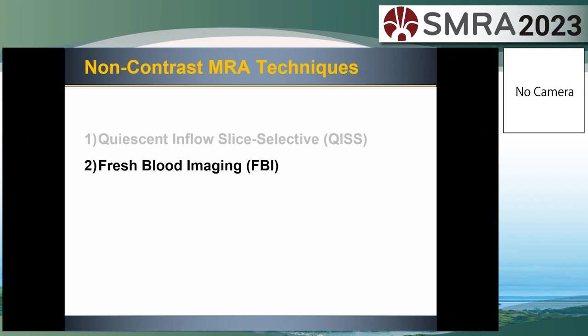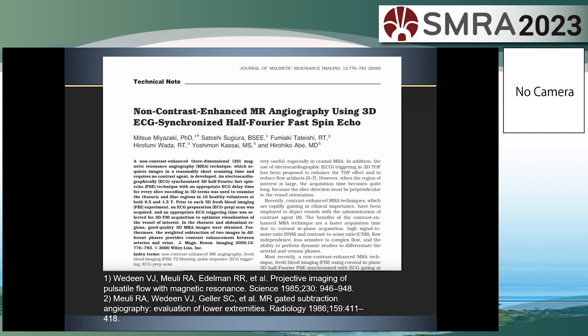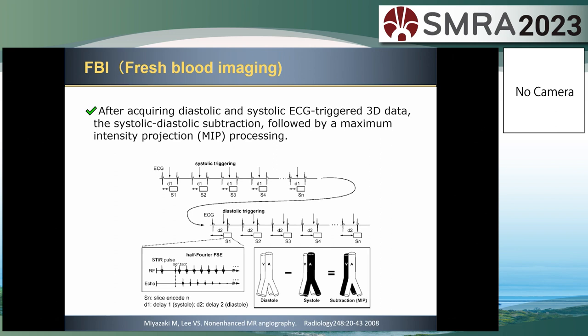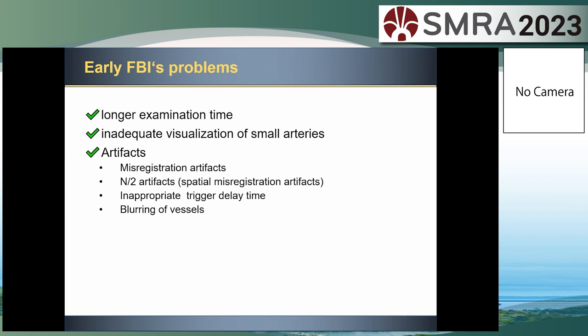Let's move on to another non-contrast MRA technique: fresh blood imaging, FBI. FBI was first reported in 2000. However, a 2D version of contrast subtraction angiography was published by Dr. Edelman's group in 1985. In FBI, after acquiring diastolic and systolic ECG-triggered 3D data, the systolic-diastolic subtraction is followed by MIP processing to get the arterial image. However, early FBI had some problems: longer examination time, inadequate visualization of small arteries, and some artifacts.